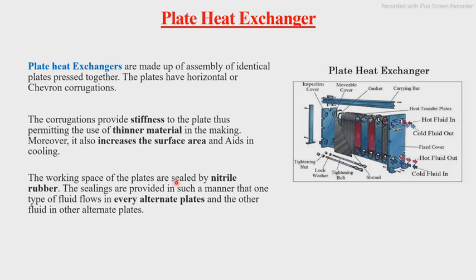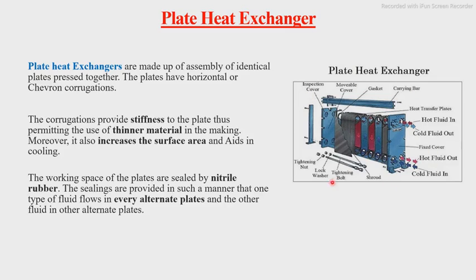The working spaces of the plates are sealed by nitrile rubber. The sealing is done in such a way that one fluid flows in every alternate plate — one plate carries cold fluid, the next carries hot fluid, then cold again, then hot again. This sequence continues till the last plate. This is the arrangement of a plate type heat exchanger, and the various parts are labeled in the diagram.